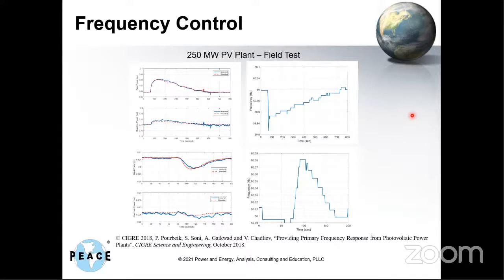Yes, they can. What that means is you have to operate the plant suboptimally. You can't convert all the incident solar radiation into power onto the grid. You have to operate at a suboptimal point, not at your maximum power tracking point, so that you have some megawatts in reserve. If you do that, this was actually played into the plant to make it think that frequency dropped and then came back.